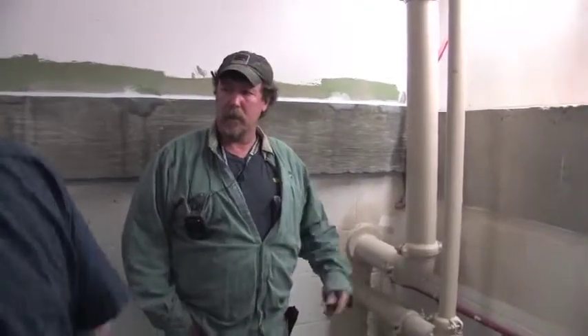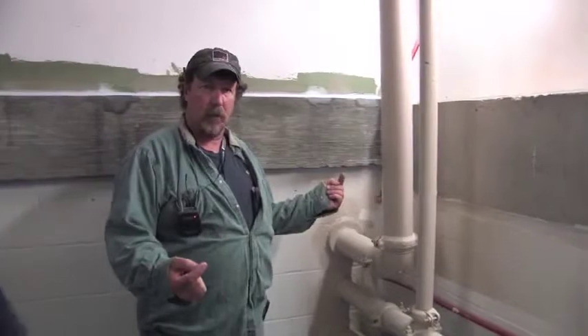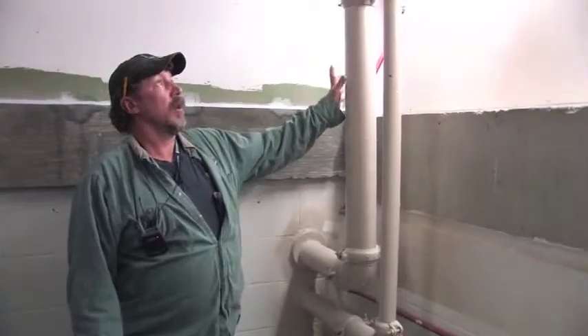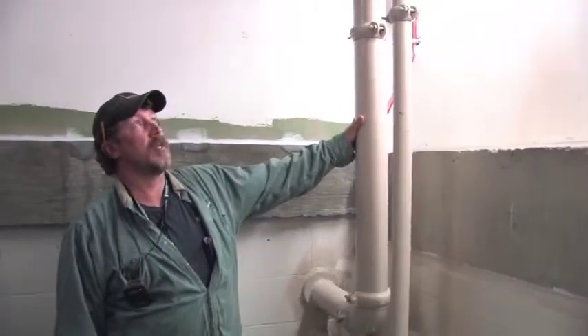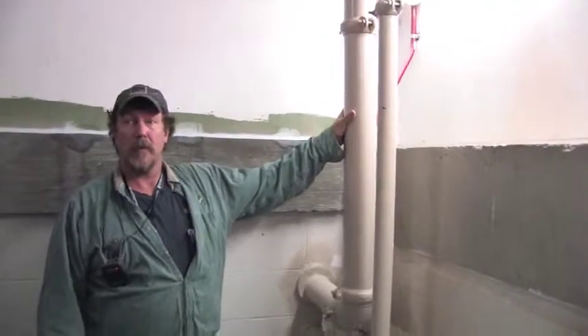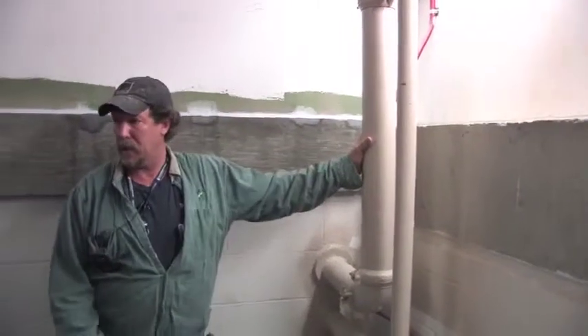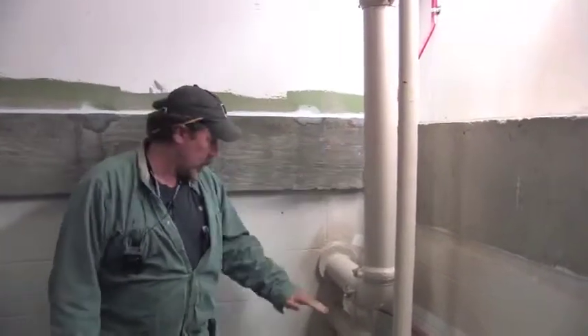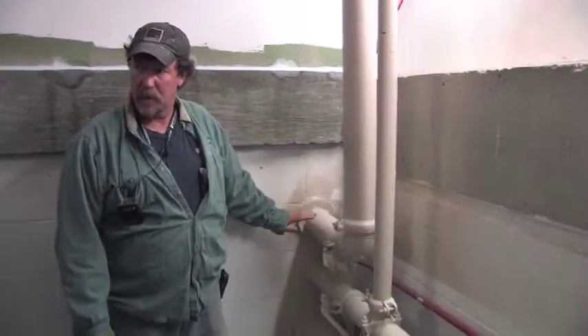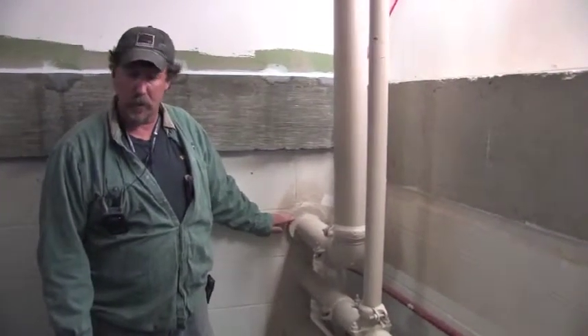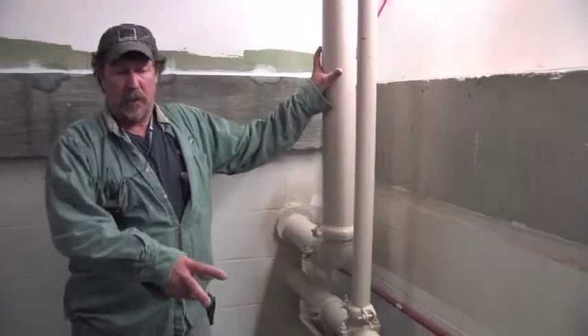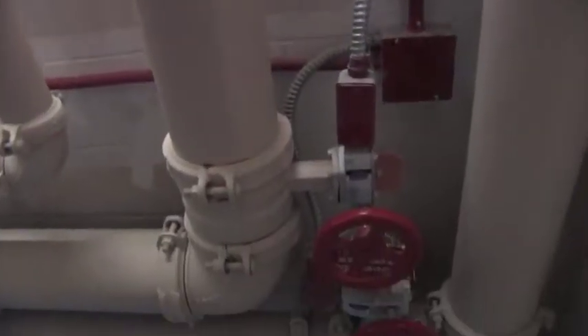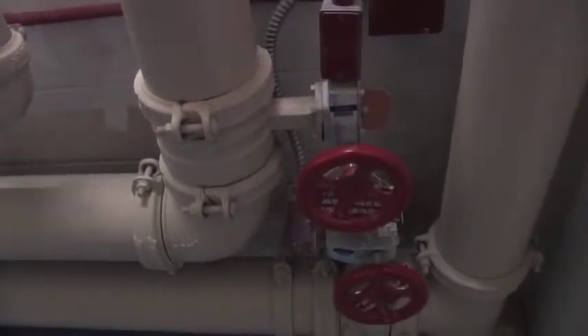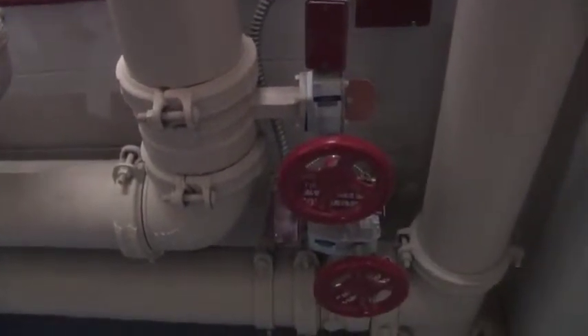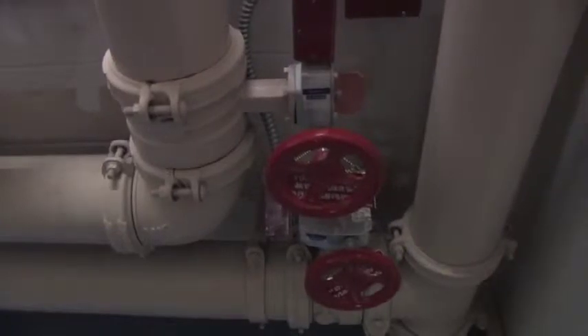Remember how I said that there's two valves to every floor? This is the other valve for the sub-basement. So there was just no room to put it downstairs. So they put it up here, piped it down, and this is valve number 2 for the sub-basement sprinkler system. And then these two valves right here are your main shutoffs for the risers. One's a high system and one's the low system. And they're listed right there on the tags.